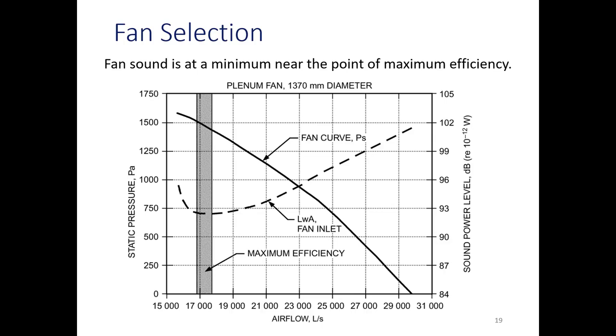So usually if you're selecting a silencer, a lot of times you can find something that adds a pretty low pressure drop, say like 0.05 inches. That would be low, but definitely far less than a quarter inch. And it's good for energy efficiency too, to have the fan operate efficiently. So you don't want to cause it to be inefficient, if at all possible.